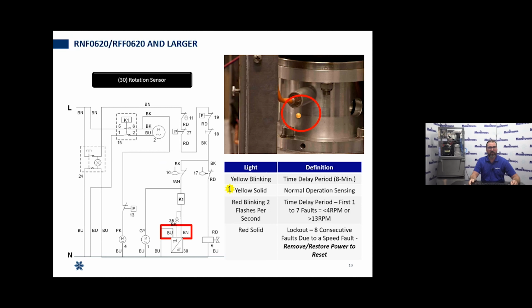So what does the flashing light on this RPM rotation sensor signify? You're going to see one of 4 different conditions. Initially, when you first start the machine, you'll see that yellow light blinking. That yellow light blinking is indicating that we are in an 8-minute time delay period. So much like on the 320, we also have an 8-minute delay here on startup, except instead of using a solid state timer, we're using this rotation sensor itself to take care of that function. So if you see a yellow light blinking, that means we are in the middle of a time delay period. We need to wait for that 8 minutes to expire, and the rotation sensor at that time should start to turn solid yellow. You'll see a solid yellow LED. Basically, that means we're past our 8-minute time delay and that we are in normal operation. Everything is good. We should be making ice.